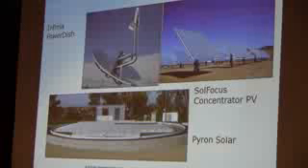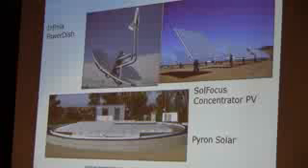And then tying in, part of my day job is doing the interconnections for large-scale solar and wind projects. In the last couple of weeks, there's been 2 large projects approved in Borrego Valley, about 500 megawatts, that will be ready by the summer. My deadline is to have our facility ready by the end of December for them. Got 26 megawatts coming into Borrego. We're building the addition to our substation so that the third party can connect. That will be up and running around July or August, so that'll be a welcome addition.